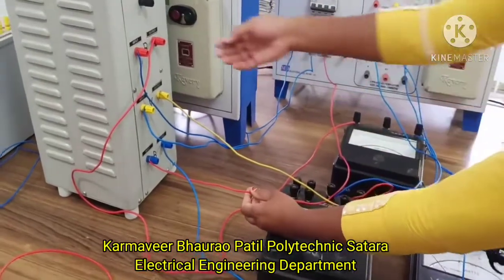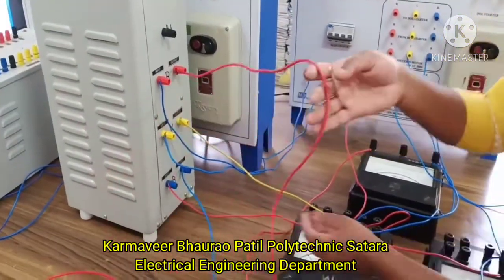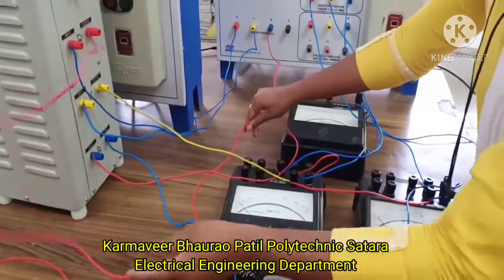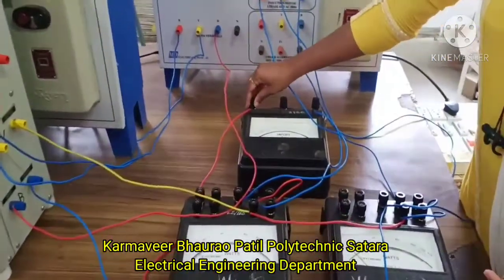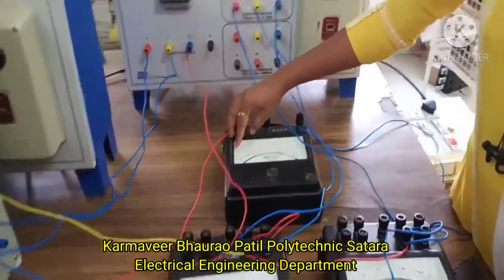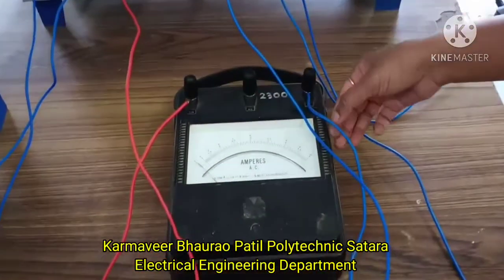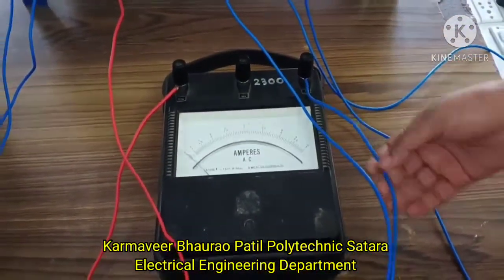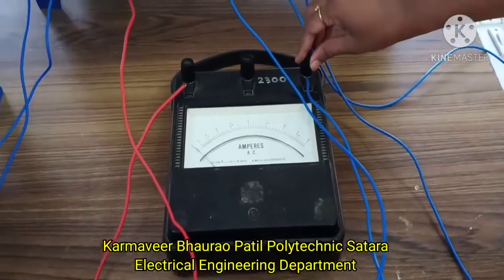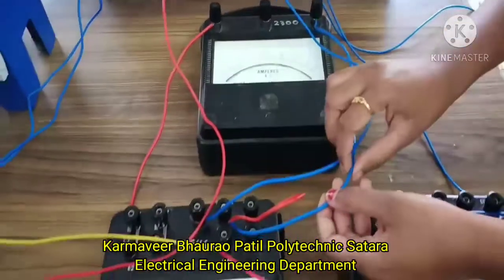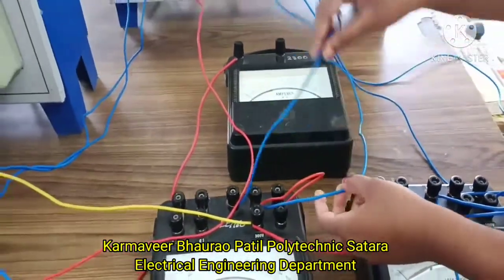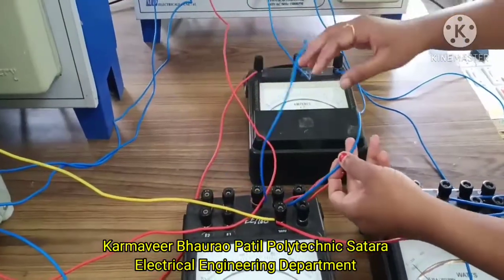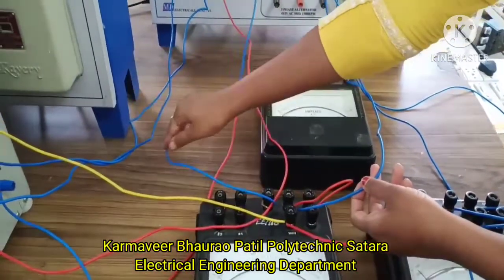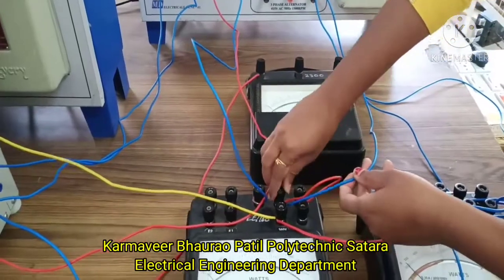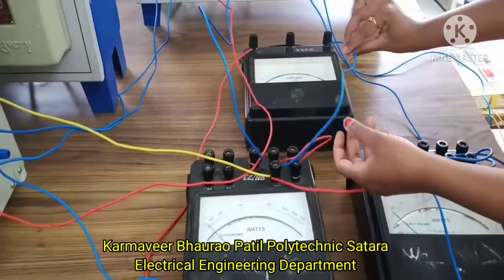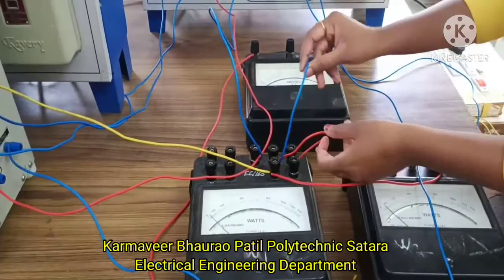Then the output from the R phase of the auto transformer will come to the common terminal of the AC ammeter, which has a range of 0 to 5 ampere. So we selected the 5 ampere range here. Then from that range connection we will connect one wattmeter. We call it W1, and we connect the M terminal of wattmeter 1 to the range terminal of the AC ammeter.